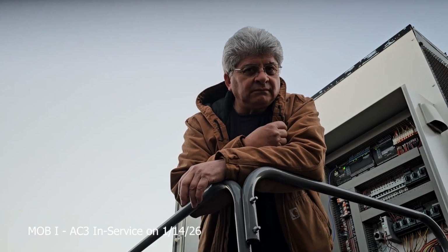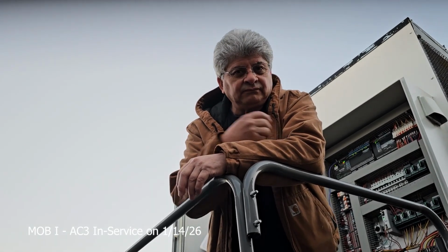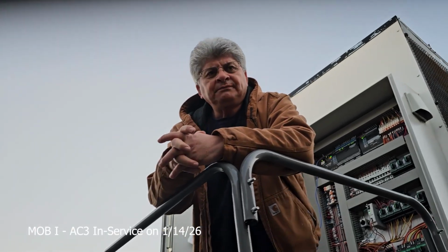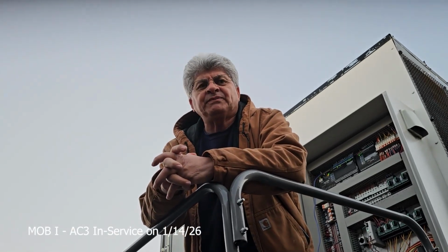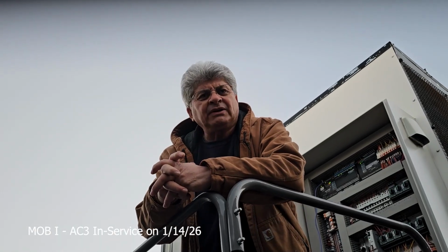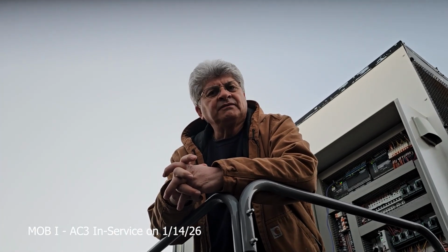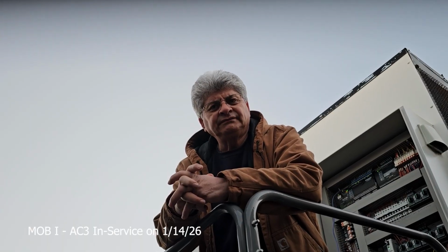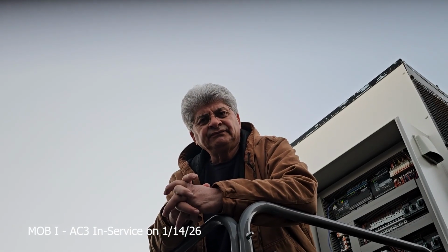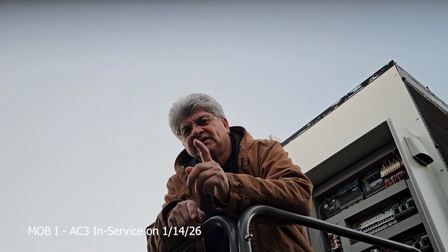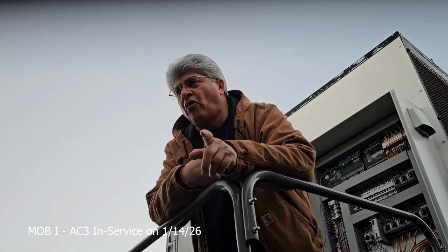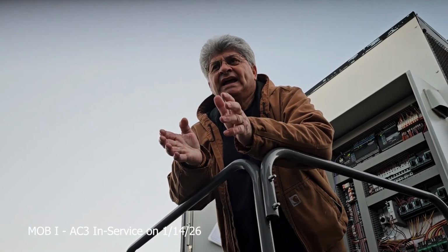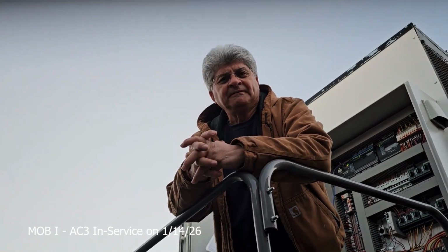How much experience do you have with this motor? How long does it last? They have an average lifespan of about 60,000 hours, 7.5 years, maybe 8 years. You'll get more because this one doesn't run 24/7. You guys shut down at 10 and start back up at 5. Yeah, but we blow it out at the beginning.